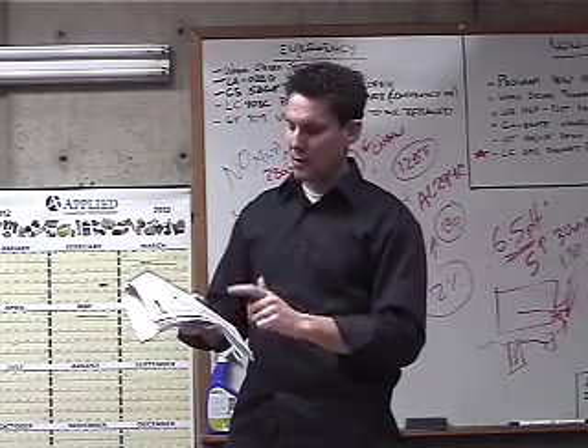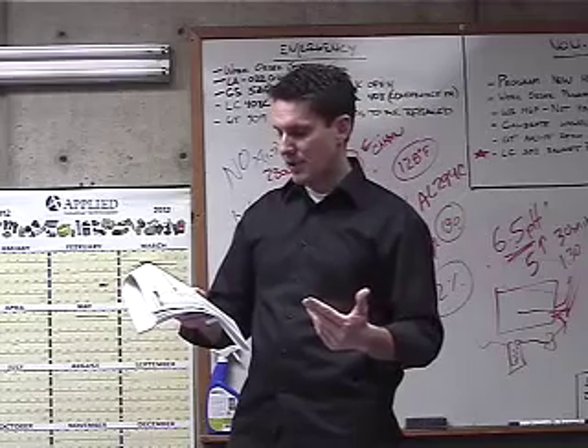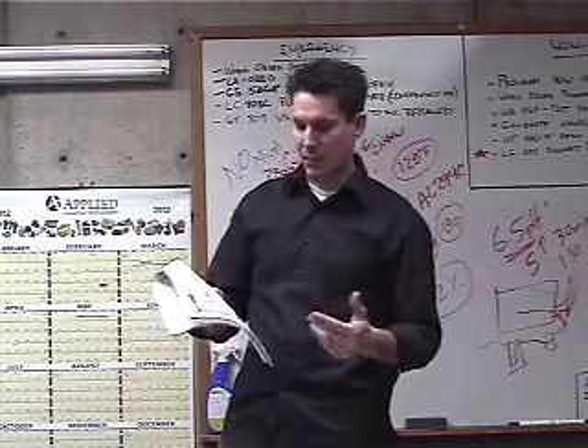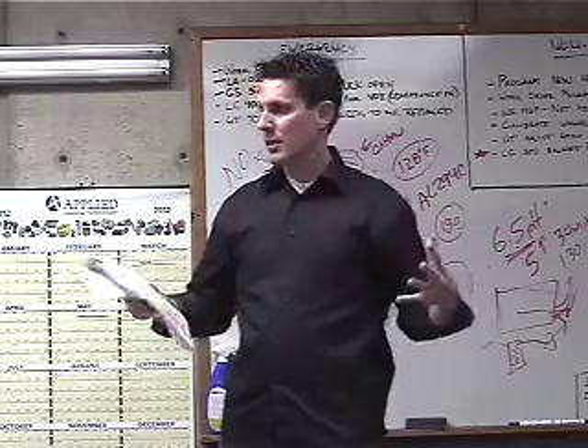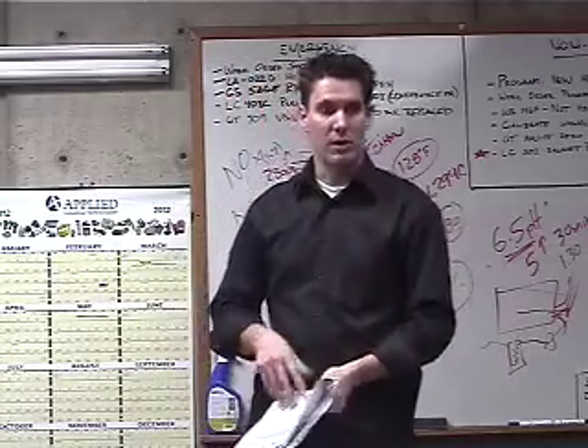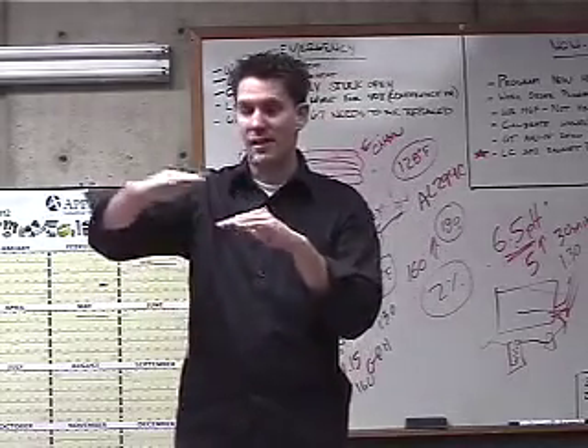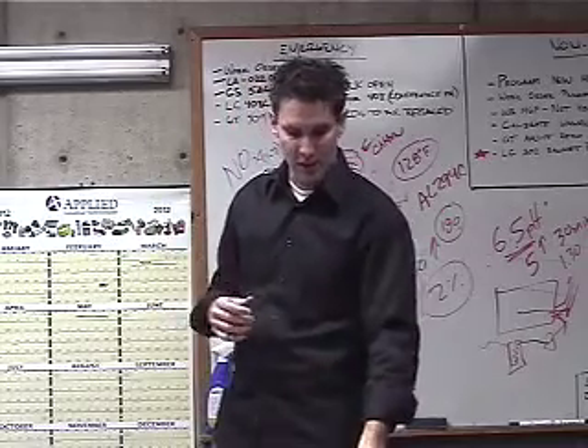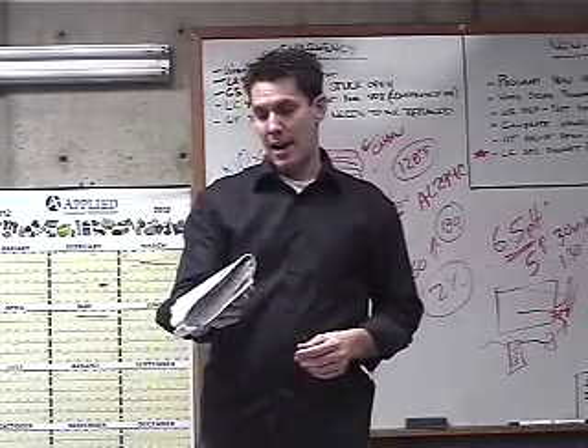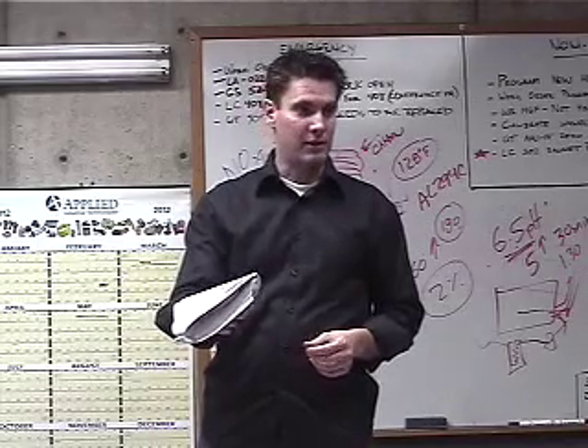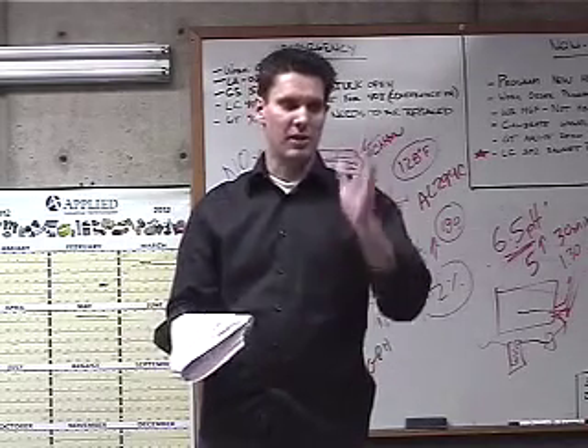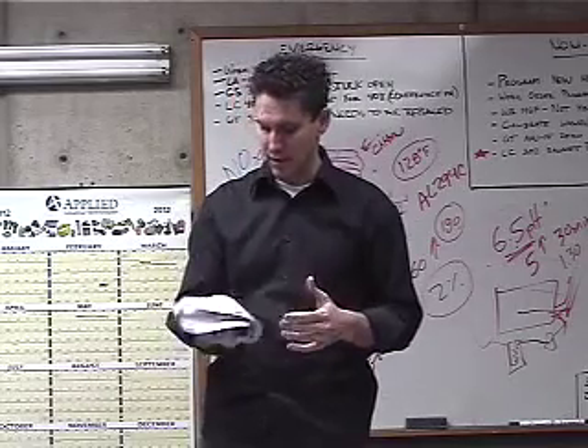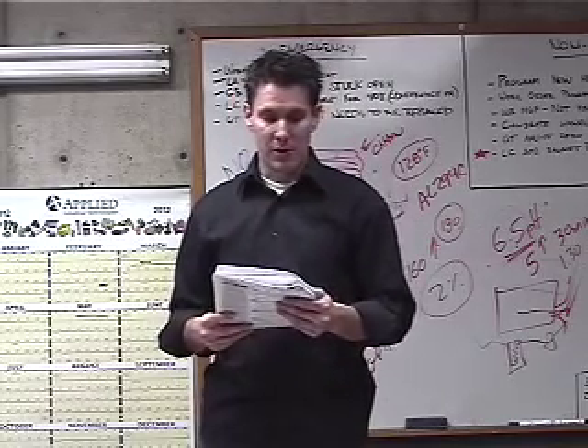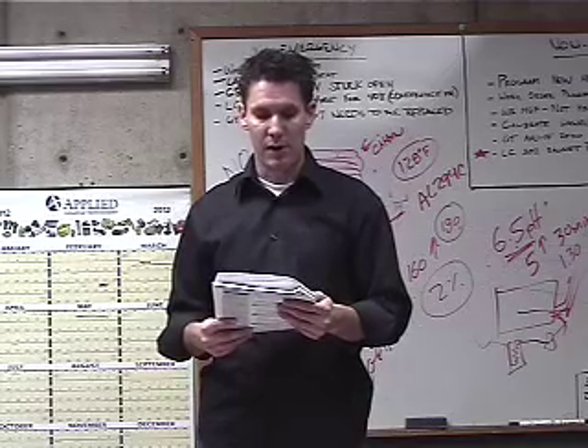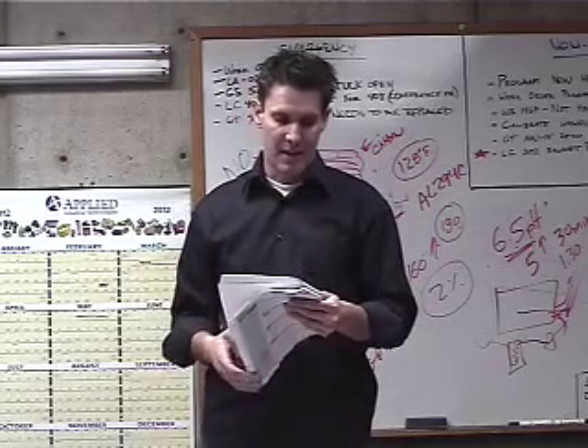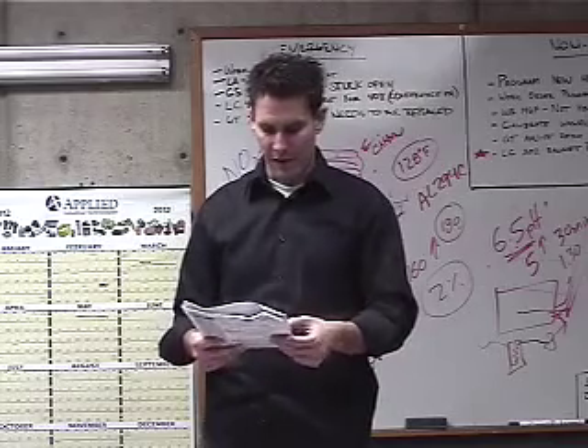So they're saying monthly you want to check that temperature. The probable cause is soot or water scale buildup on the tubes. You're not pulling enough heat off of the flue products, and so that heat's now leaving the boiler. So you have an insulation blanket either on the hot side, the fire side, or on the water side. Something's going wrong. And they say, as soon as that happens, contact us. Don't say, well, we'll just leave it be and everything's fine. Something's got to be done. Okay? Test the low gas pressure switch every month and the high gas pressure switch. Make sure that they're operating. And then you don't have the low emissions model, so you don't have to worry about the next portion.